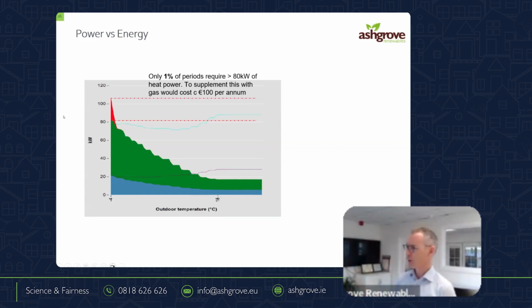The propensity seems to be, we want to put in a heat pump, we want gas or oil gone. That's grand in principle, we understand it, but it mightn't be sensible, right? You have an oil boiler or a gas boiler there. It allows the heat pump to be much cheaper. And the day, God forbid, that it's really, really cold, as we saw in Cork 10 years ago, minus 17, the gas boiler helps you that day, right?